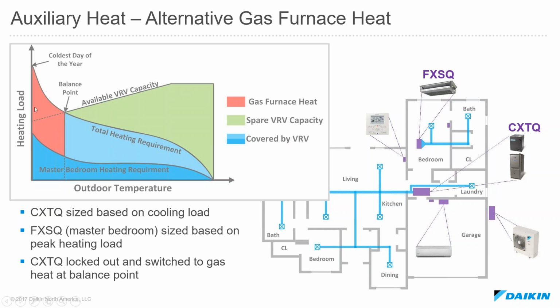So what that looks like on that balance point curve that we were just looking at, we have our total heating line. That's a sum of the heating load within the main area and the heating load within the master bedroom. So this total heating load line, once that intersects the capacity of the VRV system, we have to lock out that A coil and shut that off so that the capacity of the system is available to the master bedroom because it has no other source. So we can take the A coil, shut that off, and run the gas furnace and make that capacity available to the bedroom because there is no other option for that. So you sort of have a supplemental type of scenario going on here, or it's kind of a mix between the two things we were just talking about. We're still running the heat pump for that master bedroom, but we're running the gas furnace for the main area there.